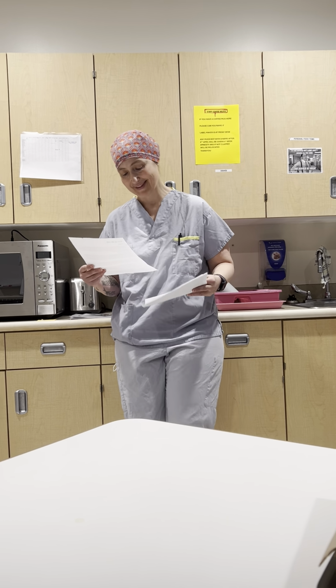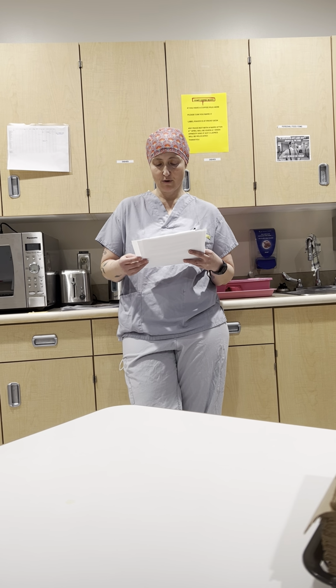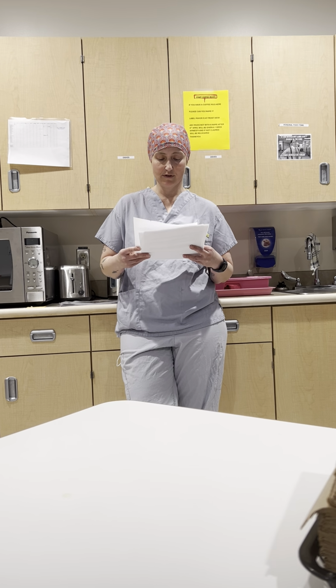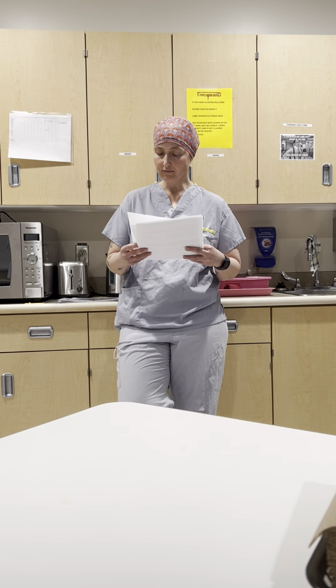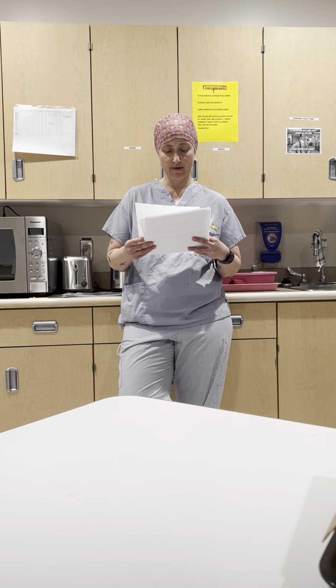The most common source is cautery from the device itself or heated tissue. Surgical lasers can ignite a fire if the beam contacts a fuel source or if the fiber is cracked or frayed, leading to escaped energy near combustibles. Fiber optic light cords distribute heat through the cable and optic apparatus, which can directly burn a patient or create a burn through the surgical drapes. Additional ignition sources include high-speed drills and burrs, bipolar electrical surgical units, and defibrillator pads.